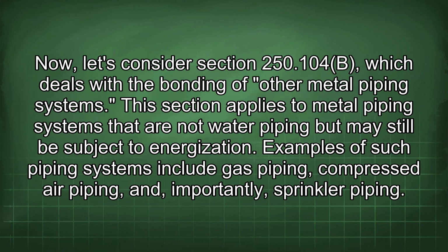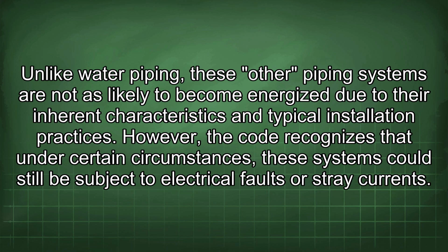Now, let's consider section 250.104(B), which deals with the bonding of other metal piping systems. This section applies to metal piping systems that are not water piping but may still be subject to energization. Examples of such piping systems include gas piping, compressed air piping, and, importantly, sprinkler piping. Unlike water piping, these other piping systems are not as likely to become energized due to their inherent characteristics and typical installation practices. However, the code recognizes that under certain circumstances, these systems could still be subject to electrical faults or stray currents.